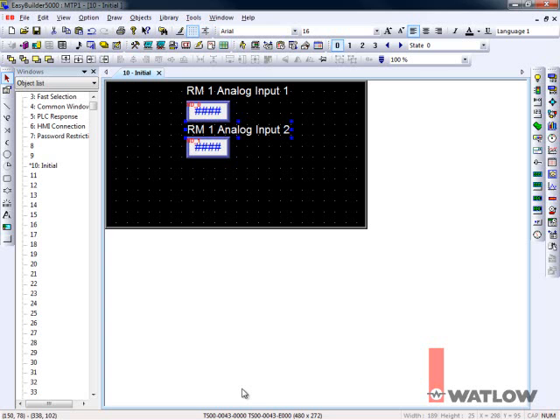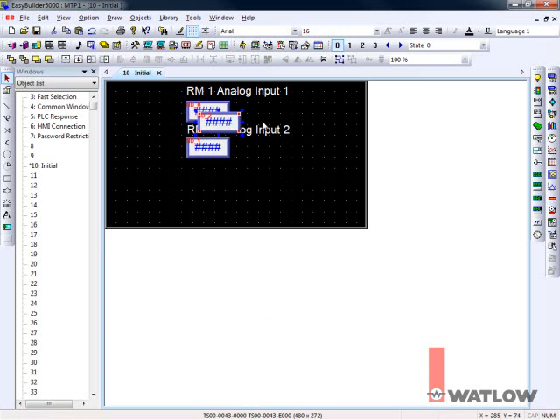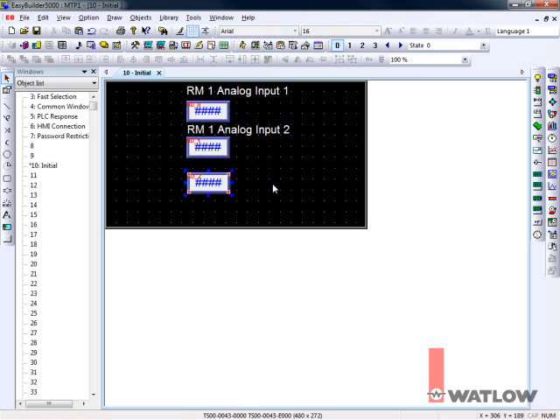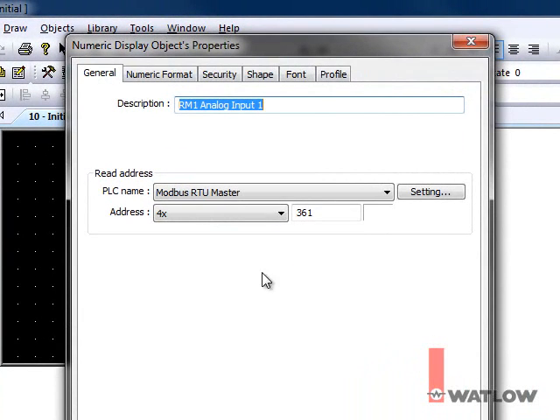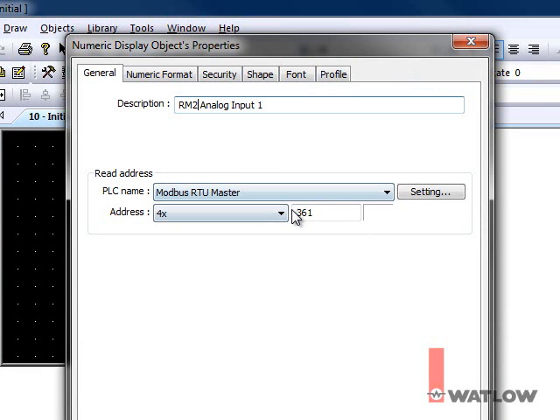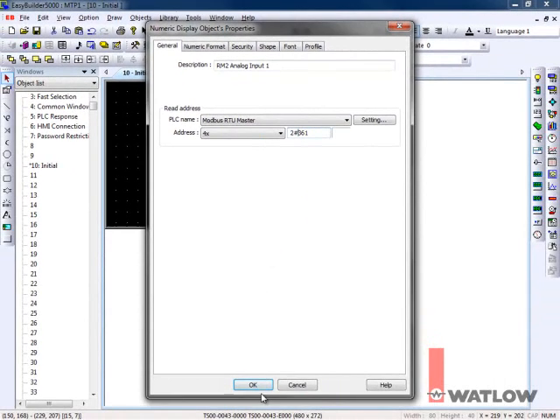To make a field that displays the value of the first analog input in the RM Control module with address 2, let's copy the first field again. Then select it, copy, paste, drag, deselect, and double-click to edit it. Edit the description. In address, insert 2 and the pound symbol or hash mark in front of the Modbus address for the first analog input value, 361. That tells the Modbus RTU master to get the data from the RM that is set to address 2 instead of the default address, 1, which we saw in the setup.